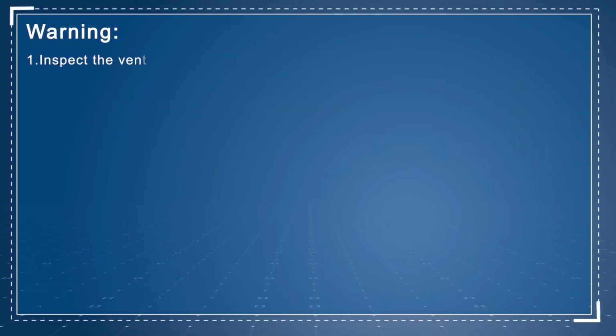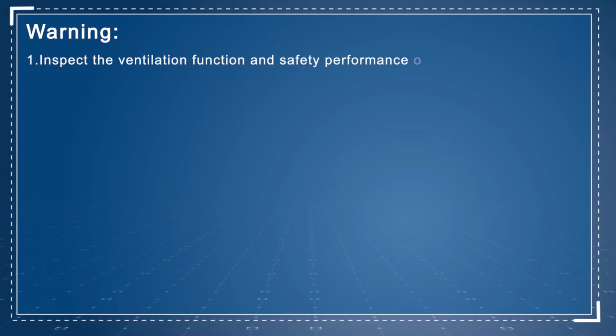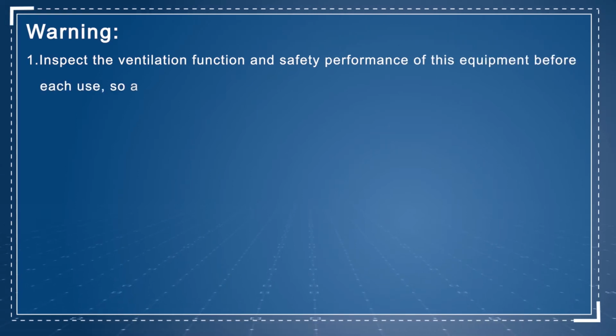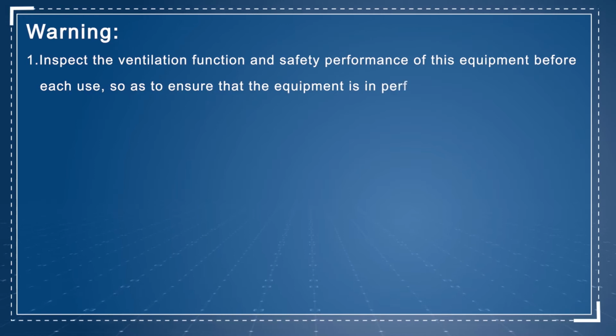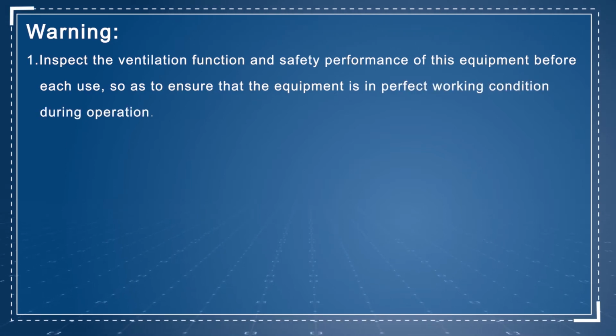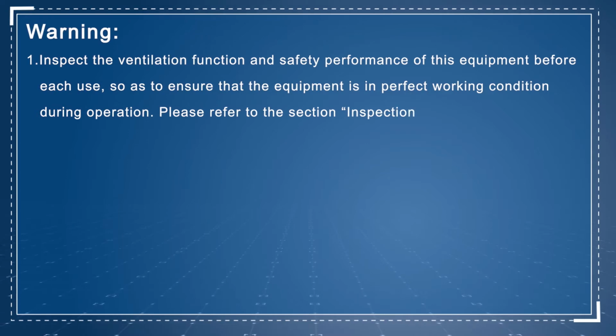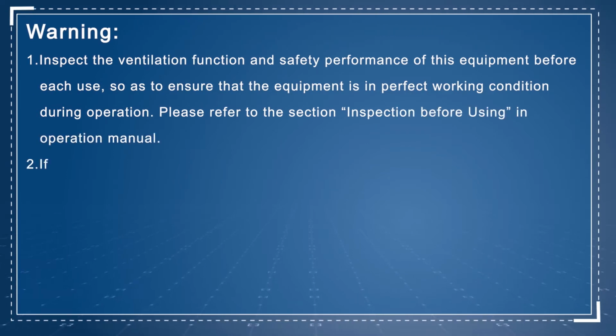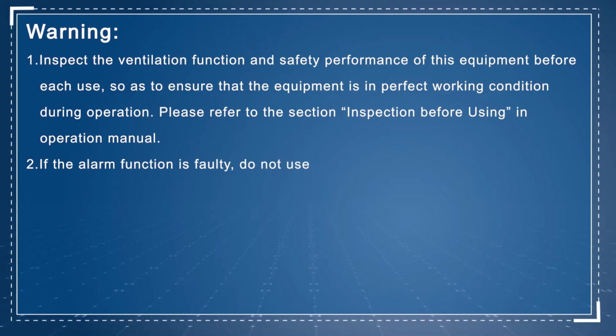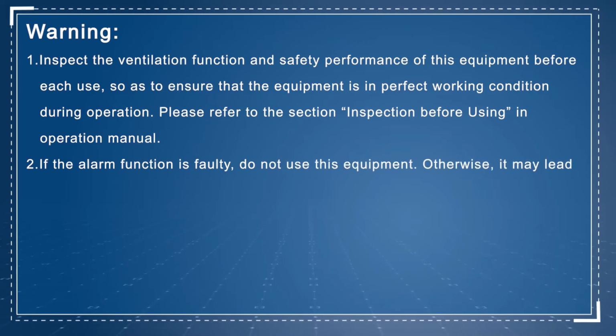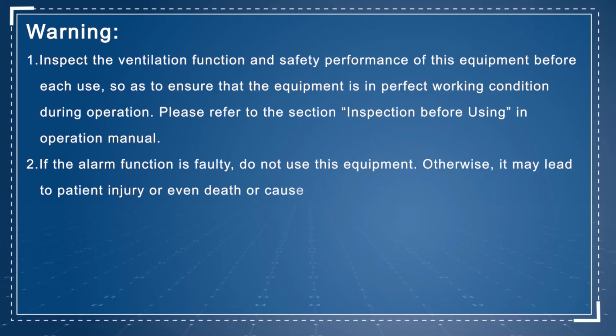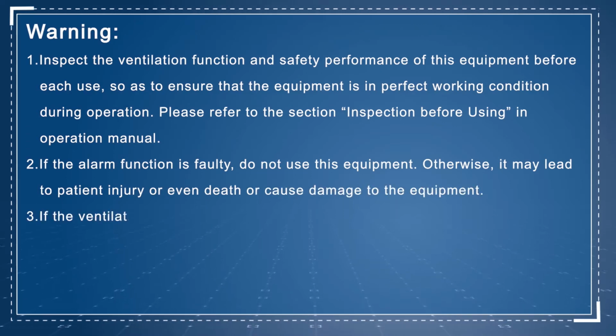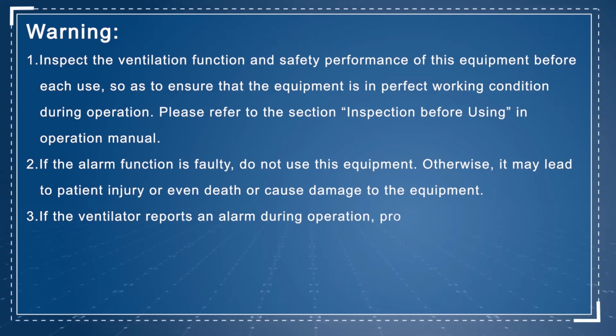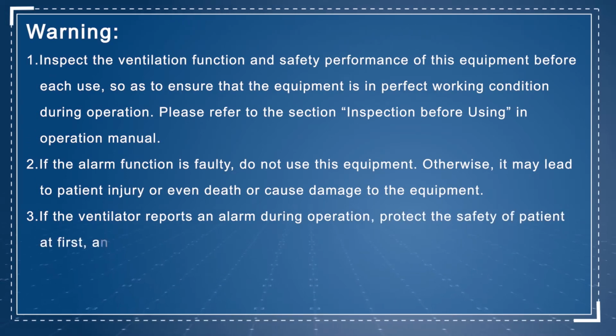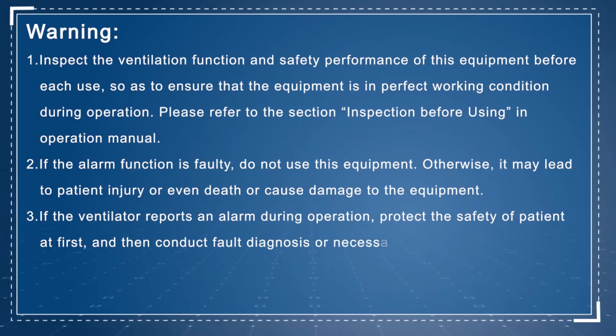Warning 1. Inspect the ventilation function and safety performance of this equipment before each use, so as to ensure that the equipment is in perfect working condition during operation. Please refer to the section Inspection before using in the operation manual. 2. If the alarm function is faulty, do not use this equipment, otherwise it may lead to patient injury or even death, or cause damage to the equipment. 3. If the ventilator reports an alarm during operation, protect the safety of the patient first, and then conduct fault diagnosis or necessary maintenance.